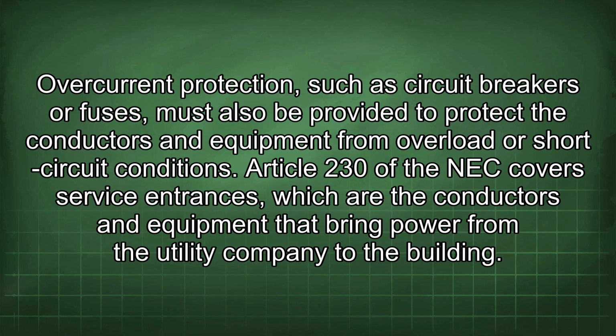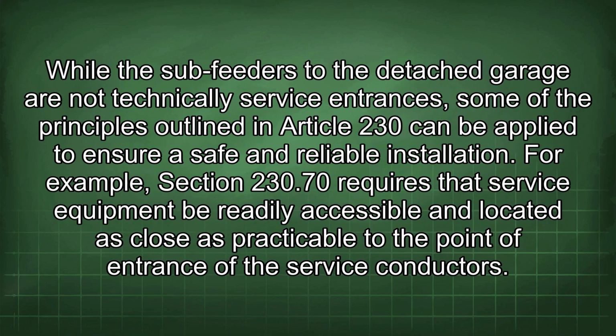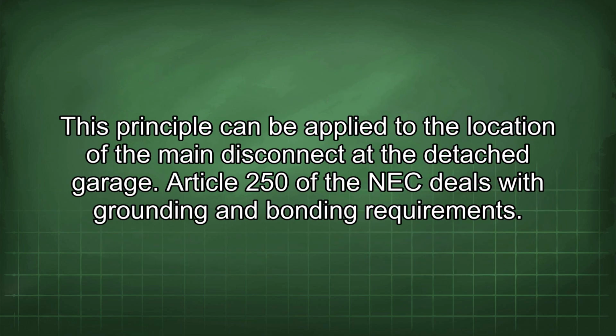Article 230 of the NEC covers service entrances, which are the conductors and equipment that bring power from the utility company to the building. While the sub-feeders to the detached garage are not technically service entrances, some of the principles outlined in Article 230 can be applied to ensure a safe and reliable installation. For example, Section 230.70 requires that service equipment be readily accessible and located as close as practicable to the point of entrance of the service conductors. This principle can be applied to the location of the main disconnect at the detached garage.